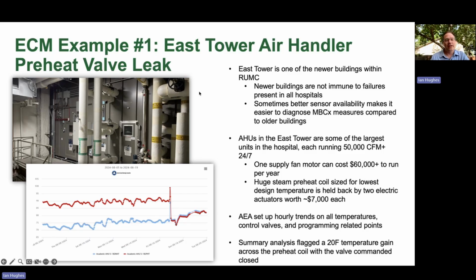It's about an 800,000 square foot patient bed tower. We had a preheat valve leak that was identified. This is a new building, I think it was put up in 2011. But I'm making the point that newer buildings aren't necessarily immune to failures. There are still challenges that happen if you're not paying attention to it. You won't see it. These AHUs, the air handling units in the East Tower, are some of the biggest on campus, each running about 50,000 CFM, and that is 24/7, 365.